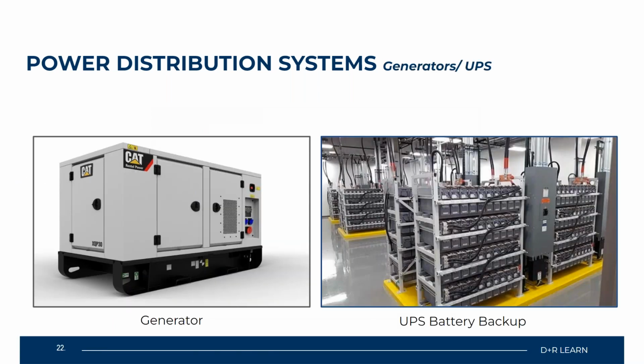Now, we also have generator and UPS operations that happen within our electrical side. A lot of the time you'll find these systems in place for redundancy. Your generator system is typically any machine that will take mechanical energy and convert that mechanical energy into electricity for transmission and distribution. So if you needed to have a secondary source of power for your facility, you can have a generator on standby that will allow you to power your facility in the case of commercial power loss.